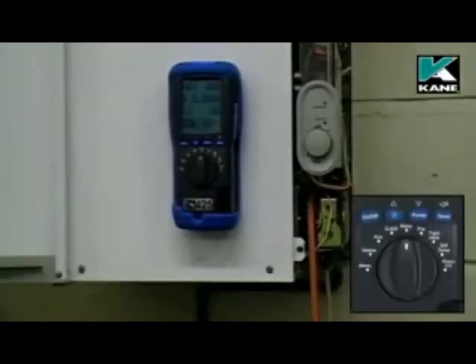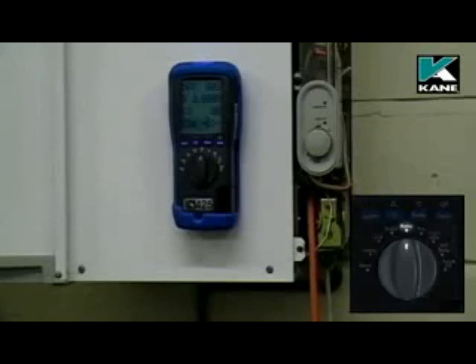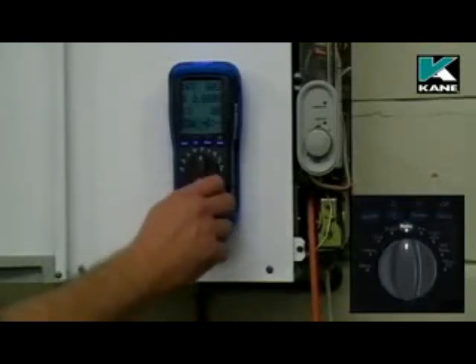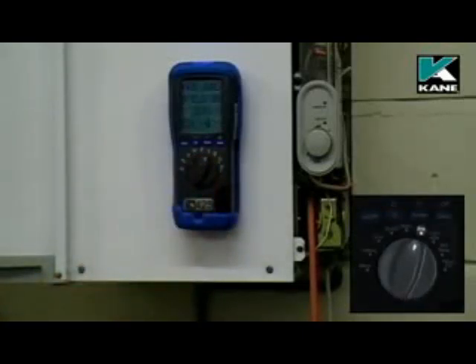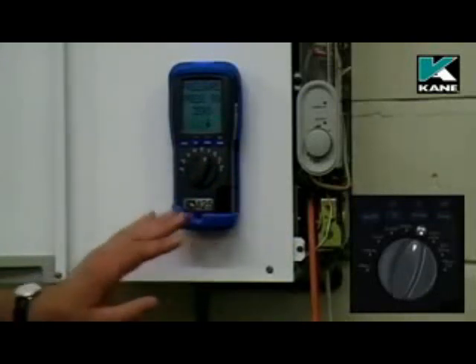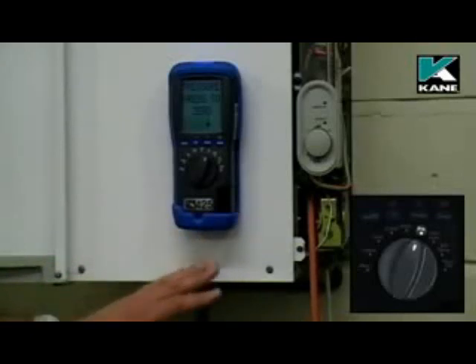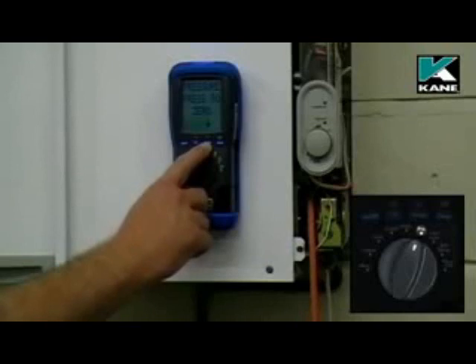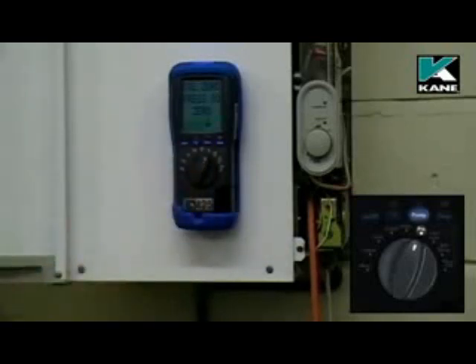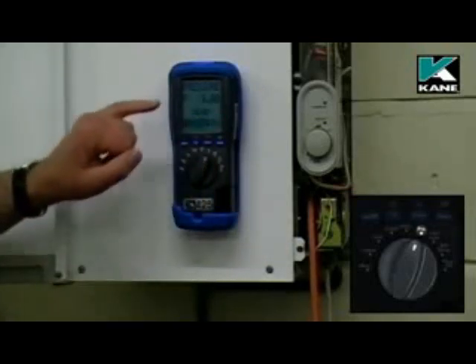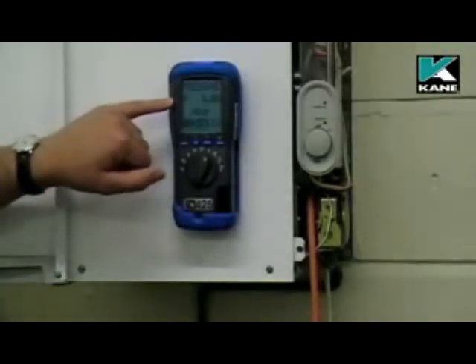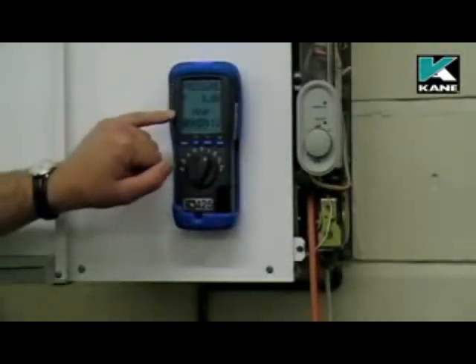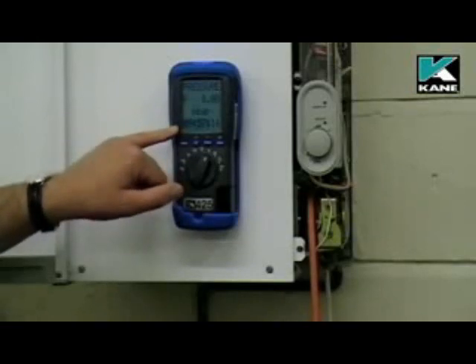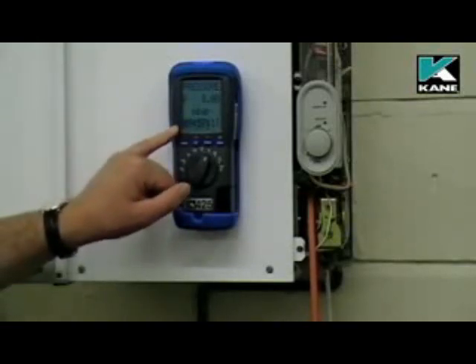To use the analyzer as a pressure meter, first move the rotary switch to pressure. You notice that the pump stops. At this stage, don't have any hose connected to the pressure meter. Press the pump button to zero the pressure meter. Now you notice on the display it has pressure to 2 decimal places, reading in millibars, and you have a clock so you can actually manually time a test if you wanted to.